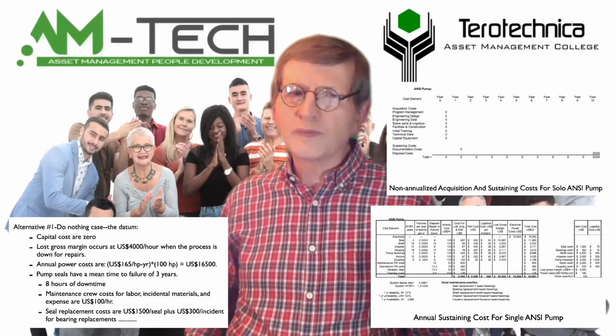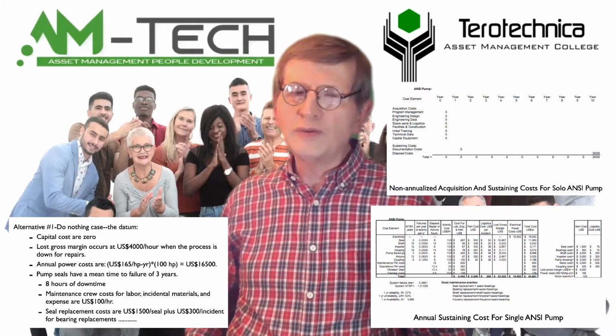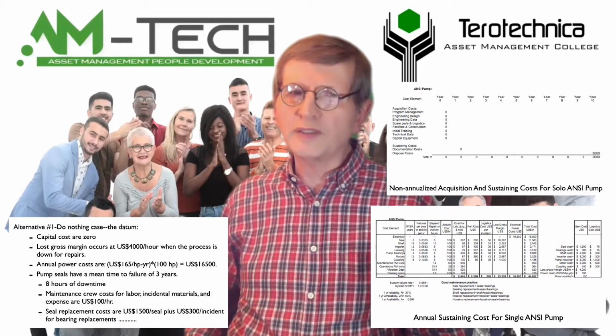Alternative 1. Alternative 1 is the do-nothing case. The present pump is left as is. Capital cost is 0, favoring the retention of this pump. However, some of the other costs are quite high. We lose $4,000 per hour when this pump needs repair. Annual power cost is $16,500.